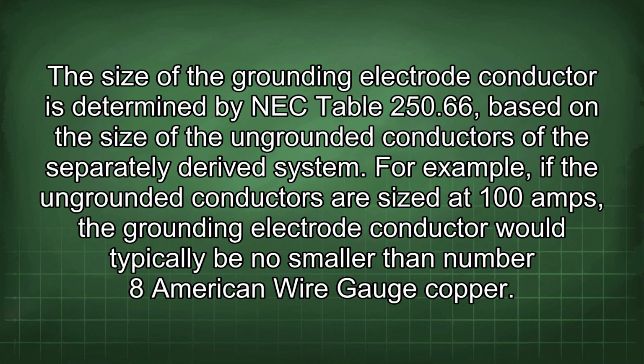The size of the grounding electrode conductor is determined by NEC Table 250.66 based on the size of the ungrounded conductors of the separately derived system. For example, if the ungrounded conductors are sized at 100 amps, the grounding electrode conductor would typically be no smaller than number 8 American wire gauge copper.